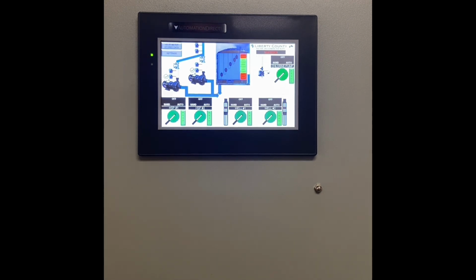Now, the alarm float, if it tips up, obviously we have way too much water in the tank. We're about to put a lot on the ground. The off float will turn off both of the running wells if they're indeed running. The lead float, as it drops down, will call for the lead pump, the lead well, and the lag float, when it drops, will call for the non-running well.